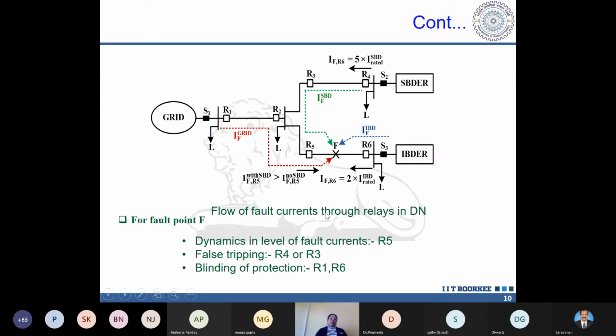The first issue is the dynamics in fault current. Which relay will see it? Dynamics means the change in fault current level. R5 will see it. Why?